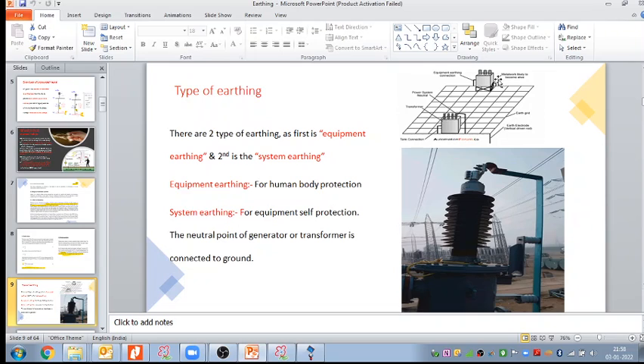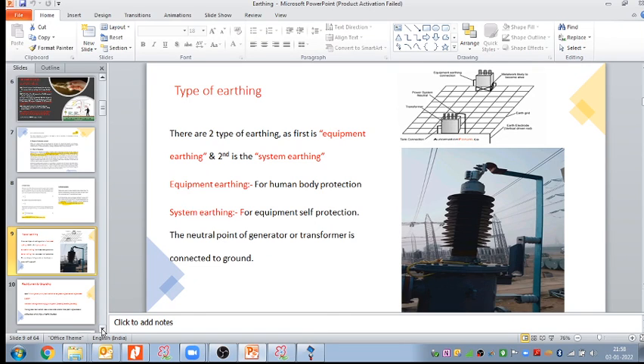We have taken this side picture. This is my earthing grid. Here we have connected the equipment to the grid, and this is called equipment earthing. And in this case, we have taken the neutral bushing of the transformer and connected it with the grid. This is called system earthing. From the side, it looks like this. This is the neutral bushing of the transformer, and on the neutral bushing we have the clamp and connector. I am making the connection, with the help of the earthing grid, to the ground. This earthing we call system earthing or system grounding. So earthing is of two types: equipment earthing and system earthing, right? This is what we discussed.